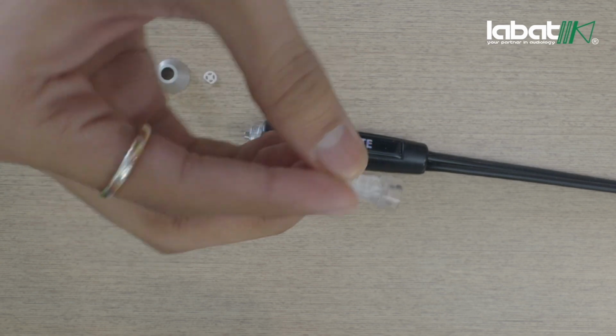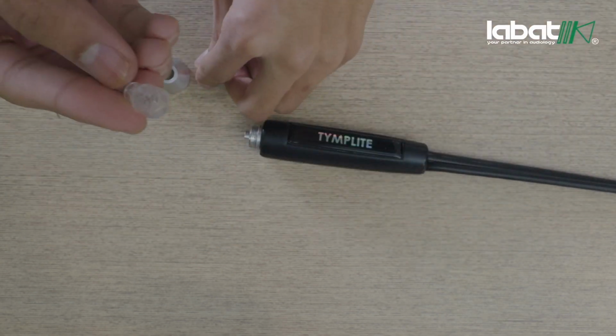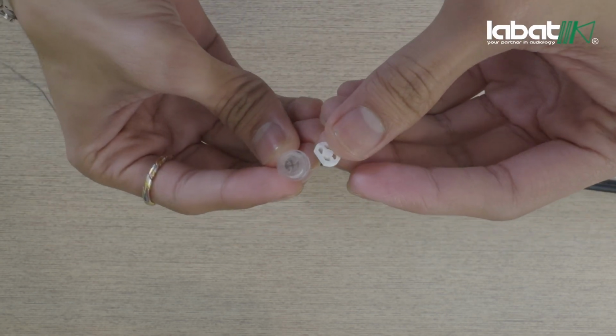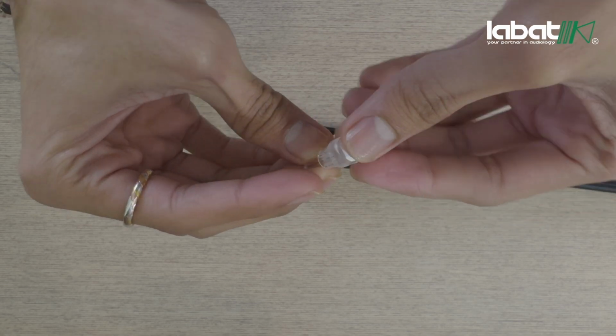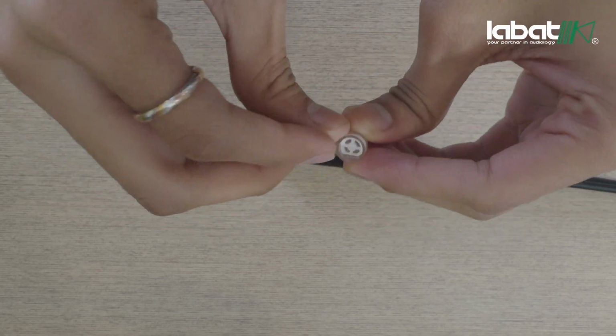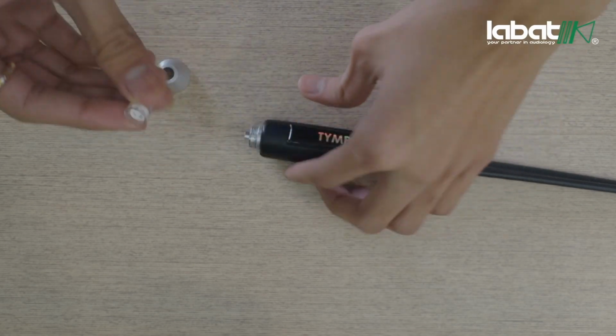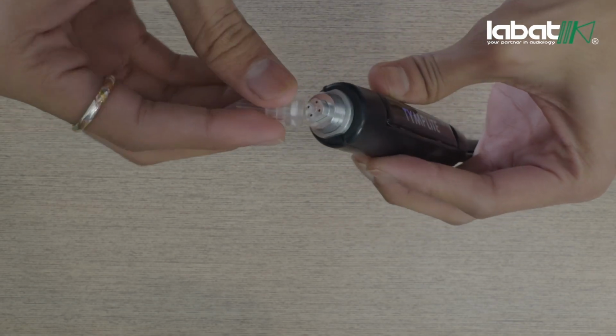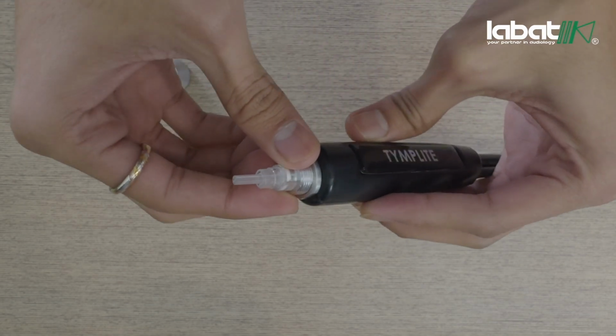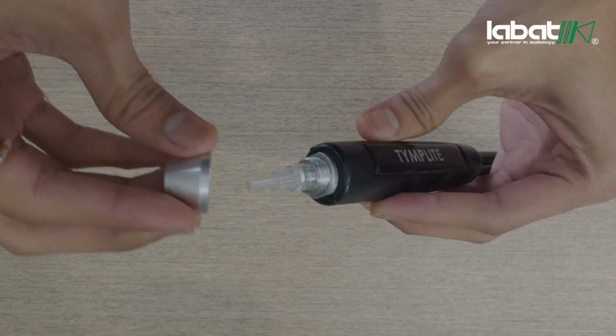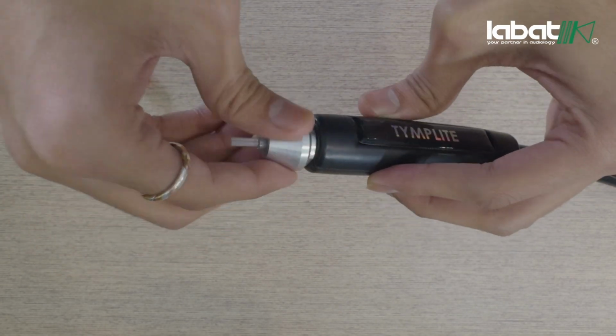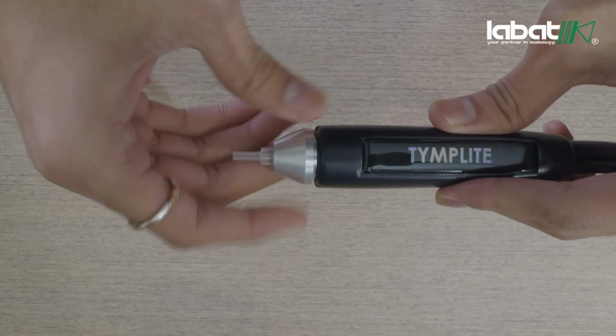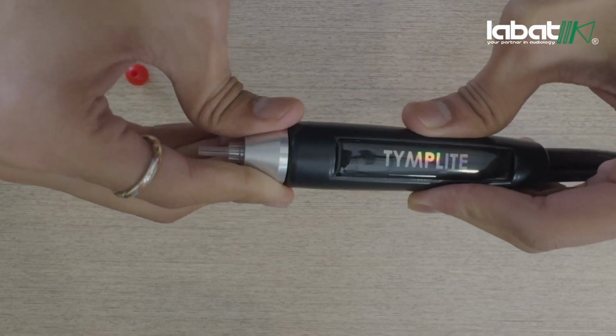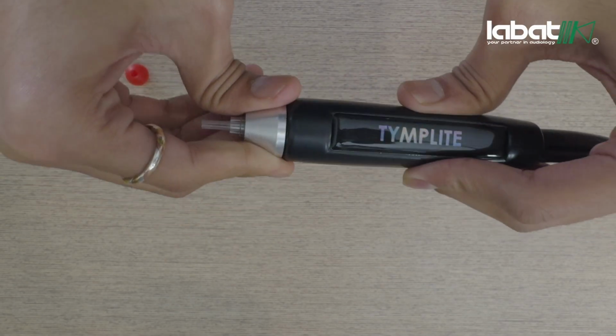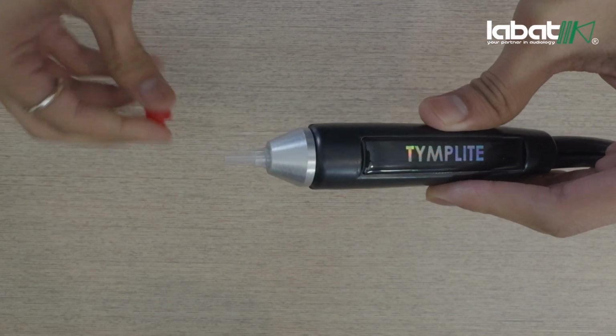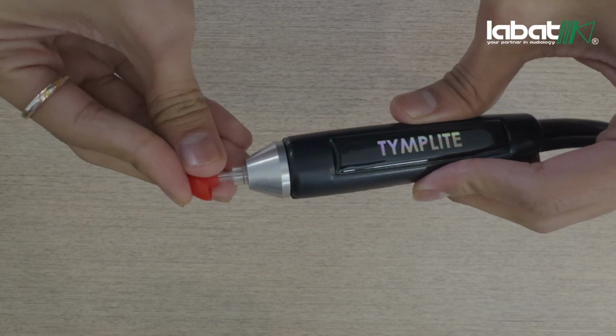After cleaning all 4 holes of the probe tip properly, gently place the seal rubber inside the probe tip. Place the assembled probe tip onto the nut assembly with correctly aligned grooves on both parts. Place the nose cone onto the probe head and rotate it in the clockwise direction and tighten it. Ensure that it is secure but not over-tightened. Finally, place the ear tip back onto the probe.